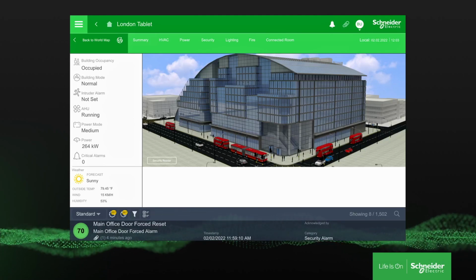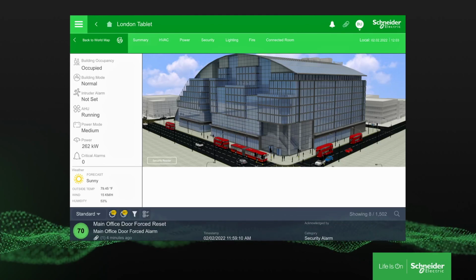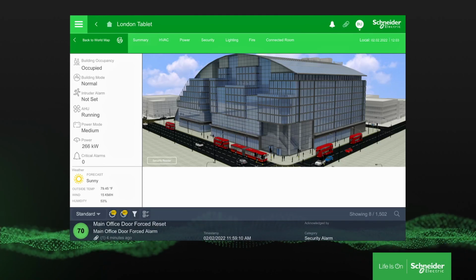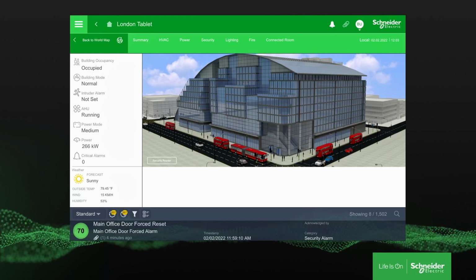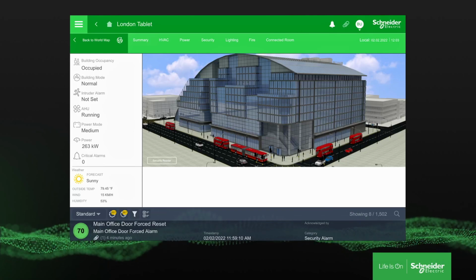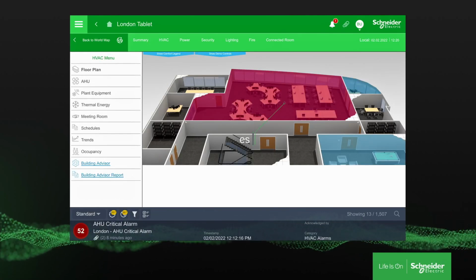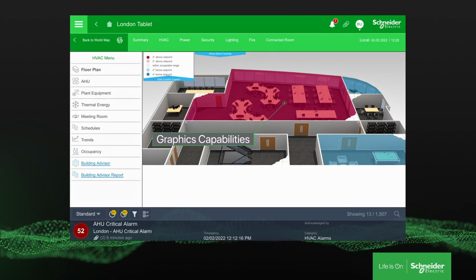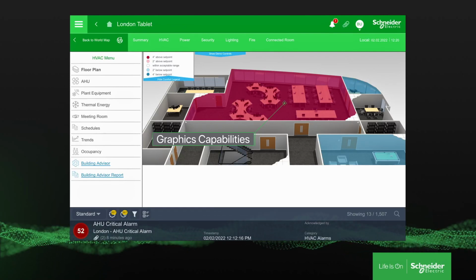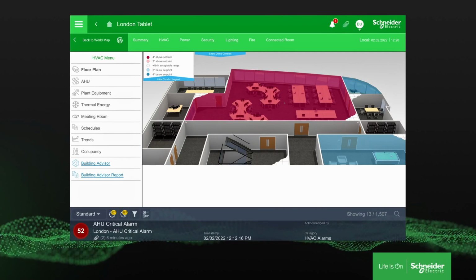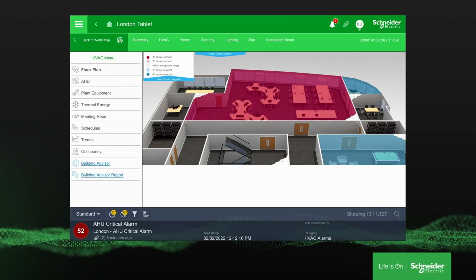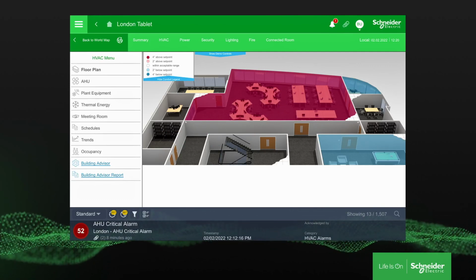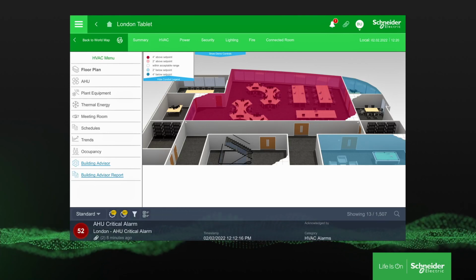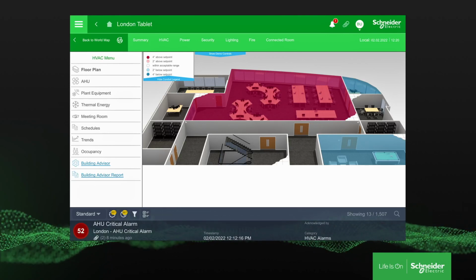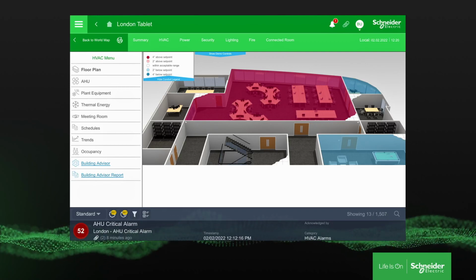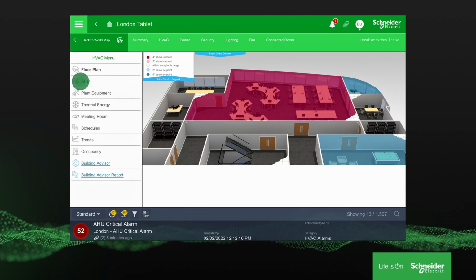The facility manager can see that the building operation has raised several alarms he needs to address. He will click into the office to quickly diagnose the issue. Powerful graphics capabilities allow fast visual assessment of the building and its systems. You can easily see with these colored temperature overlays on the floor plan that the main office is too hot. You can also see there are some alarms in the alarm banner and they're from the air handling unit that is serving this floor. So let's check the air handler.